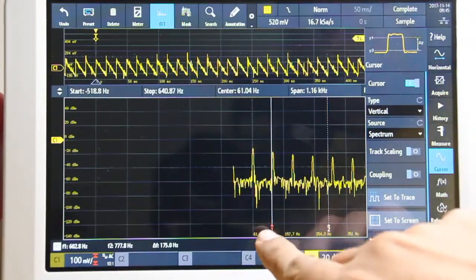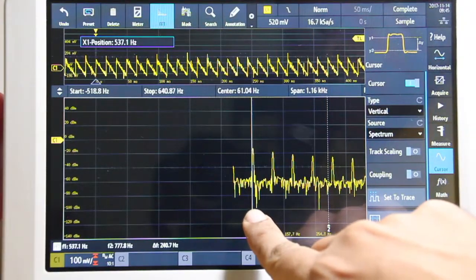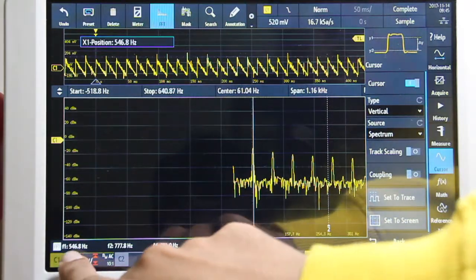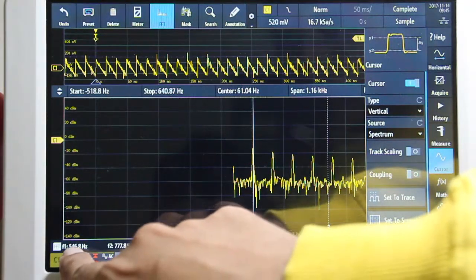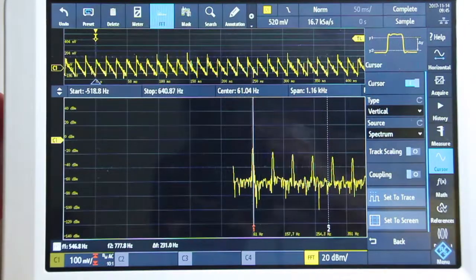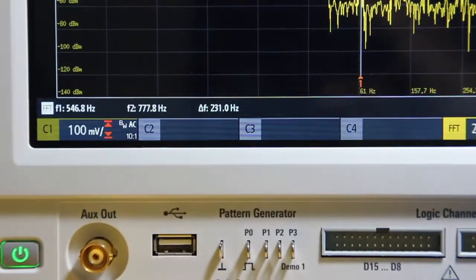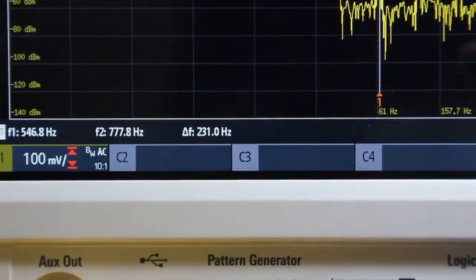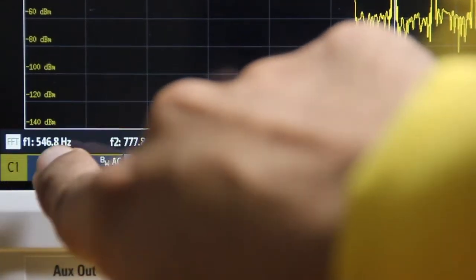So put cursor one right about here. It says F1 is 546 Hertz. No, no. Take a look at this, so cursor one is at 60 Hertz but this thing says cursor one is at 560 Hertz. If I move this around, that's wrong. So big problem.